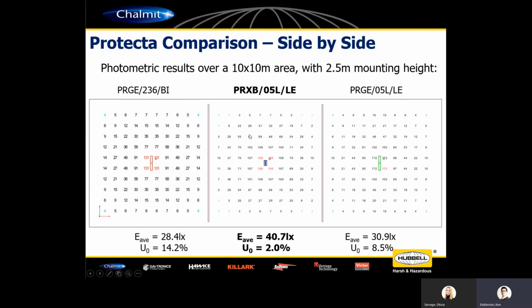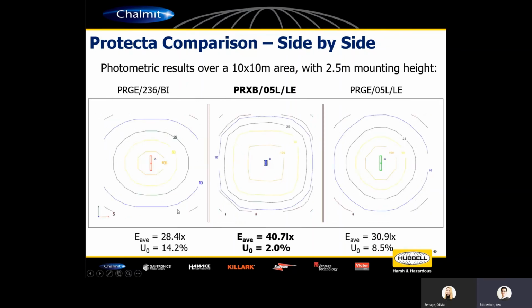For those of you that have done lighting design before, you will know that uniformity is a real challenge, especially for hazardous areas. So there's a lot of trial and error required to meet the minimum uniformity requirements of typically 25 to 40%. Okay, but in this one-to-one comparison, the Protecta X has a low uniformity purely because of two things. One, it's got a flat diffuser, so you're not going to quite get as much sideways throw as you would with a deep bowl diffuser. And secondly, your fluorescent type products will typically have a better sideways throw, as you can see from this image here, these isolux contours. Because your fluorescent tube is essentially 360 degrees of light, it will always have a little bit more sideways throw than your new LED products.